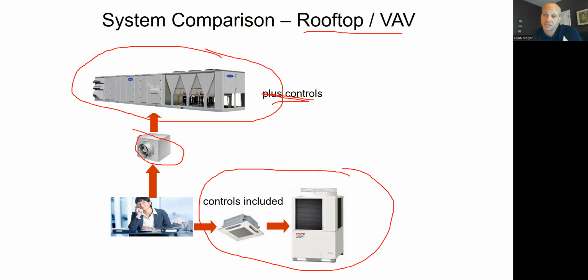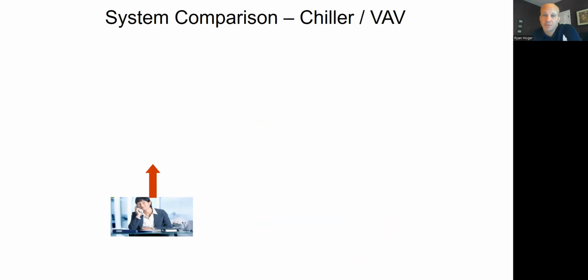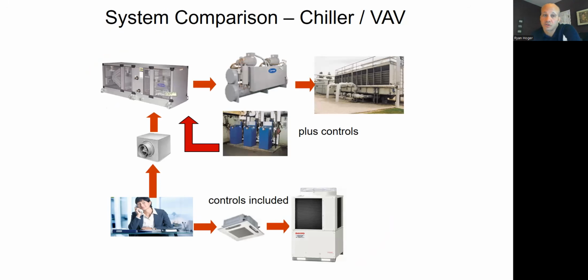In most cases, the VAV rooftop will beat the price of this. Not always, but most cases, depending on whether you can get ductwork in there or not. If you have existing ductwork, then the VAV rooftop almost always wins to replace the existing VAV rooftop. Right? It's easy. When you get to more complicated systems, then that's not necessarily true. And by the way, VRF could beat the rooftop on pricing sometimes, but usually not.